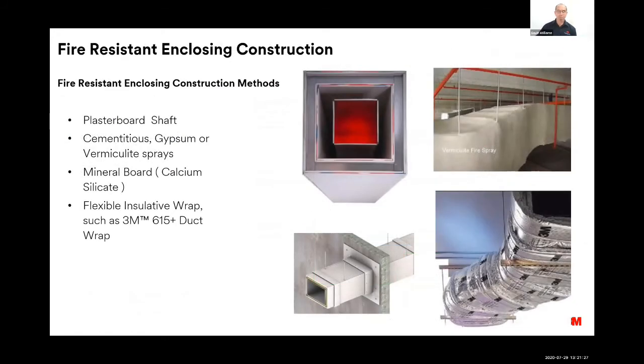So now I'll just talk about the different methods that can be used to enclose fire-resistant or fire-rated ductwork. The 4 most common methods in Australia and New Zealand are a plasterboard shaft, or a cementitious gypsum or vermiculite spray, mineral boards such as calcium silicate, and flexible insulated wraps such as 3M's 615 Plus duct wrap.